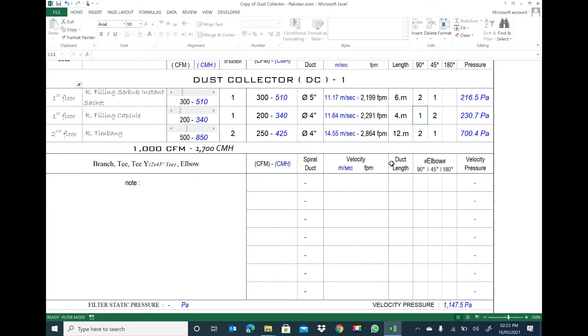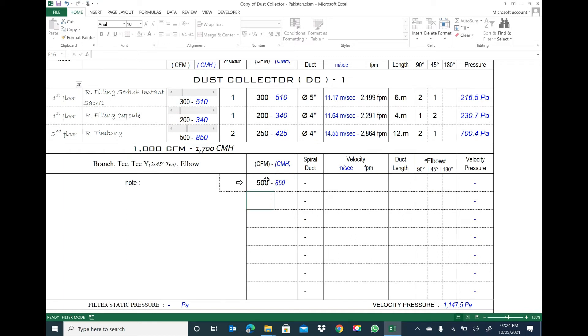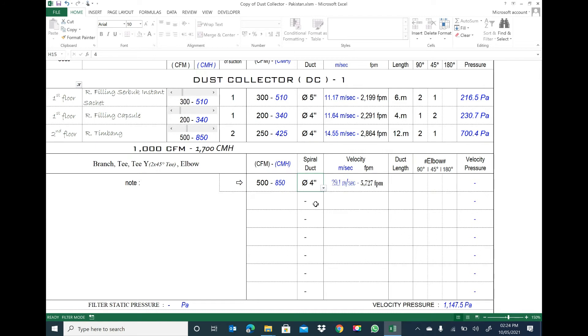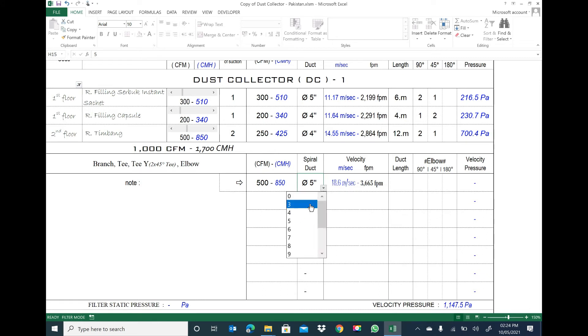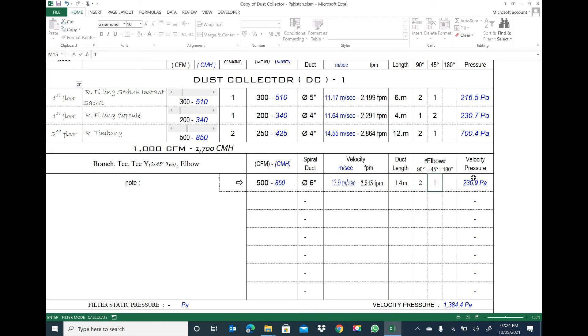This inside clean room duct connects to the main duct. For the main duct, the CFMs from each room are added together — 300 plus 500 gives a total. We check the main duct size: at 4-inch the velocity is 29 m/s, which is too much; 5-inch is still high, so we go to 6-inch, which is acceptable. The duct length is 14 meters, with one 90-degree elbow and one 45-degree elbow. The total velocity pressure is calculated.